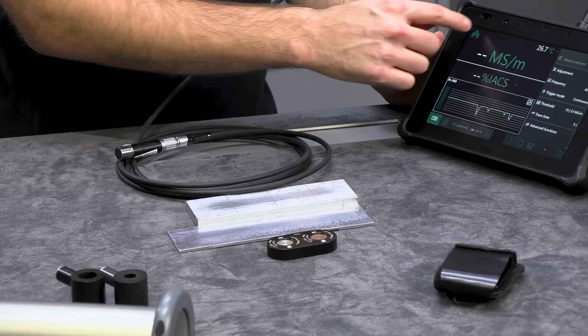This goes even deeper if you are in a parameter like the test frequency. There it is described in detail what the test frequency is, what you change with it if you switch it, and what effect you have on the penetration depth of the eddy current signal. And additionally, you get the information what else you can do with this parameter. You can do two-frequency testing, mixing, and so on. Everything is described here. And for some parameters like the gain, there's also an animation. And this we will also look at on the instrument on site.